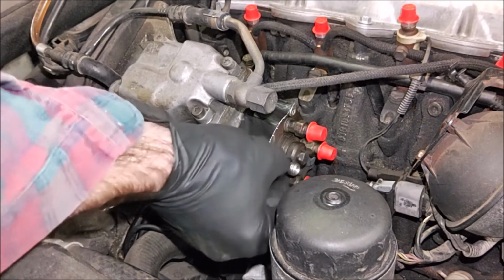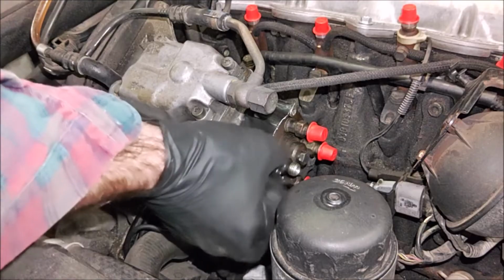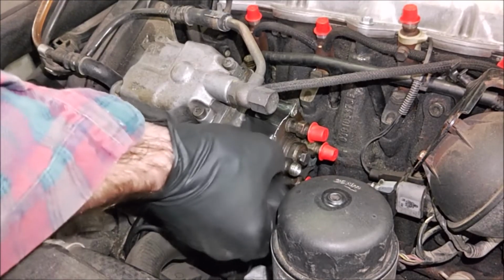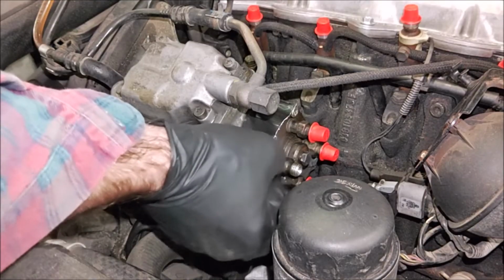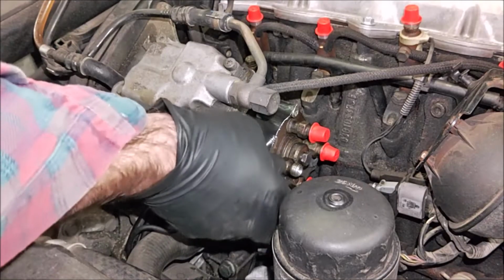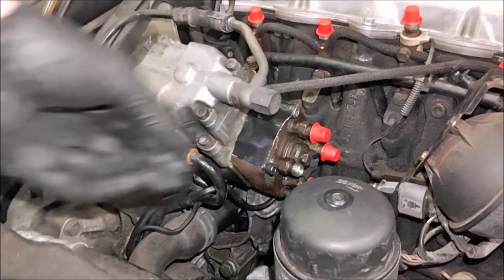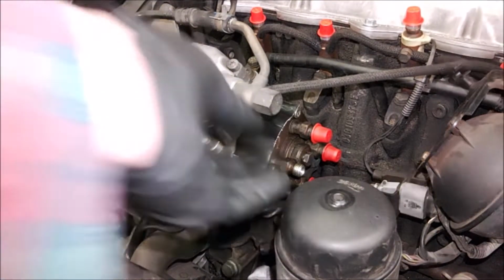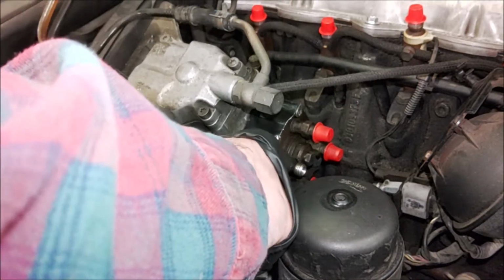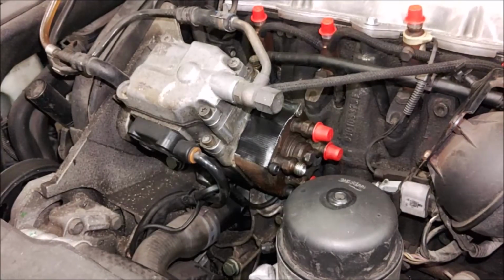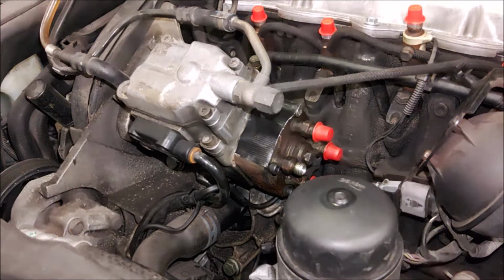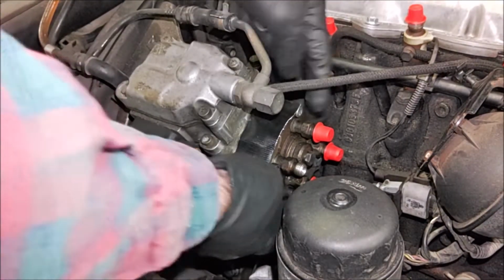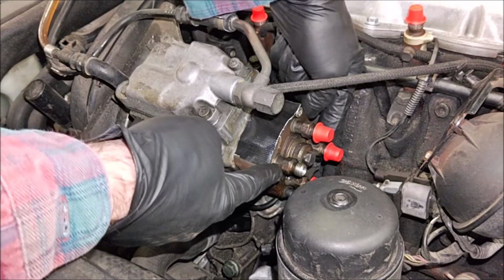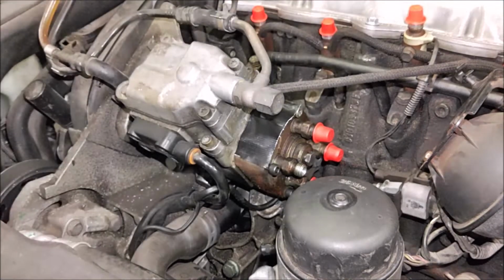Now don't overdo it, because these are going into an aluminum body, you don't want to strip the threads. Okay, that is snug. Now according to the instructions, it says to back it out a half turn once it's snug. So I'm snug now, so I'll back it out about a half turn. Right there, and I'll leave it, and then I'm going to remove these two opposing ones, so we should just have two opposing Torx screws left in the pump head.